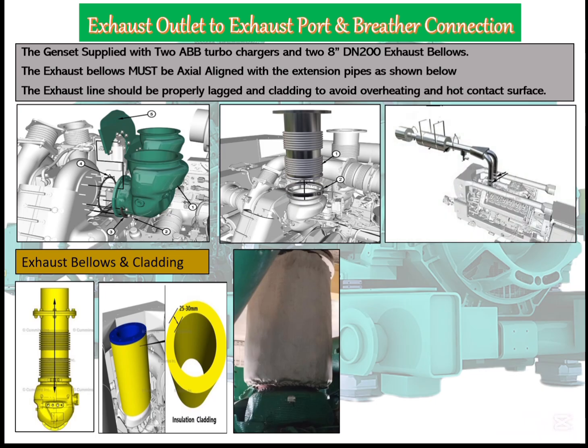Then this is the final picture. We have two exhaust lines, then it goes to the exhaust port and finally is released into the air. Or if you are using CHP, you can collect the heat from here and take it to your boiler, fan, absorption chillers, or any other device you want to run on heat. In CHP, you can collect heat and reuse.